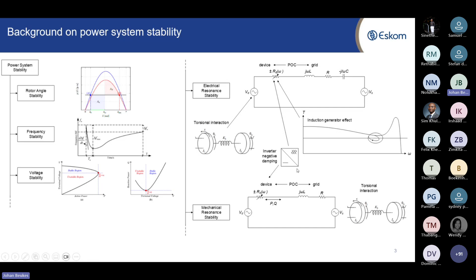Yeah. Okay. To come back, electrical resonance stability: if we have series compensated lines, we can create a resonant point. And when you have negative damping at that resonant point, the system can become unstable, and equipment that typically generates that negative impedance is torsional interactions on generators, especially the nuclear generators, and then you have the induction generator effect. But the third one is inverter-based resources creating negative resistance at certain points. You can now also have mechanical resonance stability, where you have a torsional interaction and a negative inverter creating a negative resistor to that torsional interaction at the torsional interaction frequency.